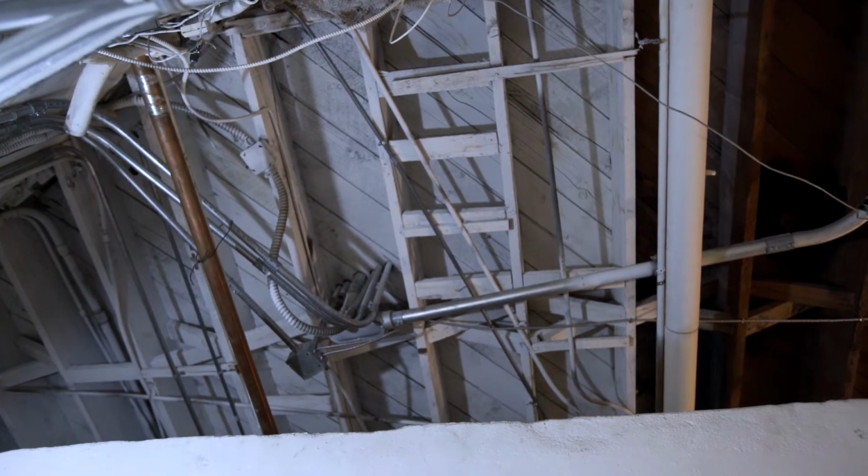that water. We need to provide fire separations between the floor levels, and the floors are constructed out of wood in a large area of the cathedral. Anywhere there's wood, it's combustible material, we should really be protecting those areas from spread of fire. One way of doing that is by installing a fire suppression system, like a sprinkler system. So we would like to do that in the lower areas of the cathedral to prevent any spread of fire to the upper level of the cathedral.